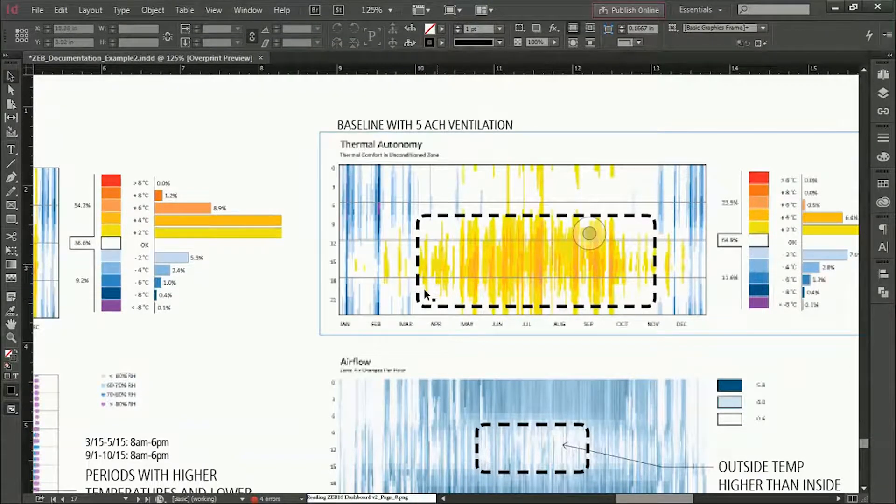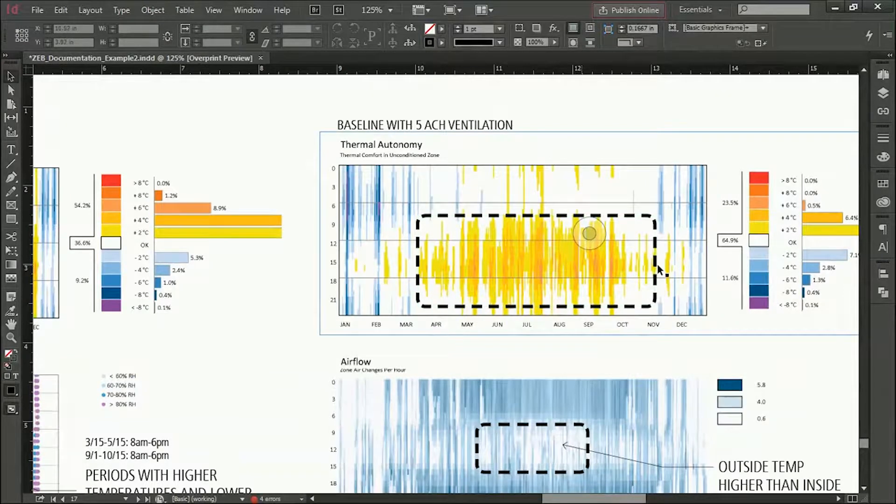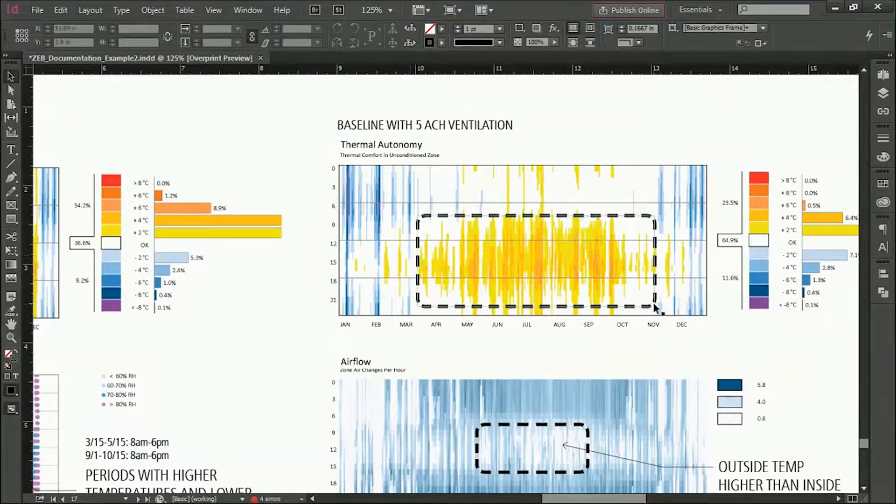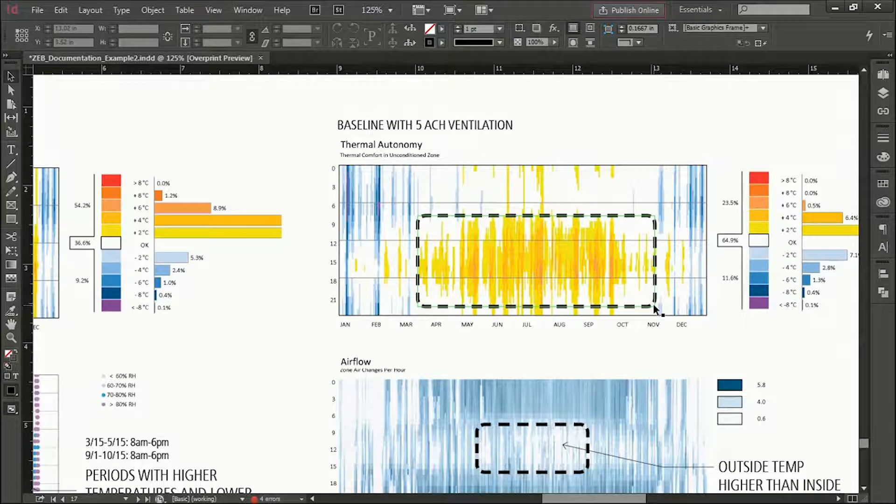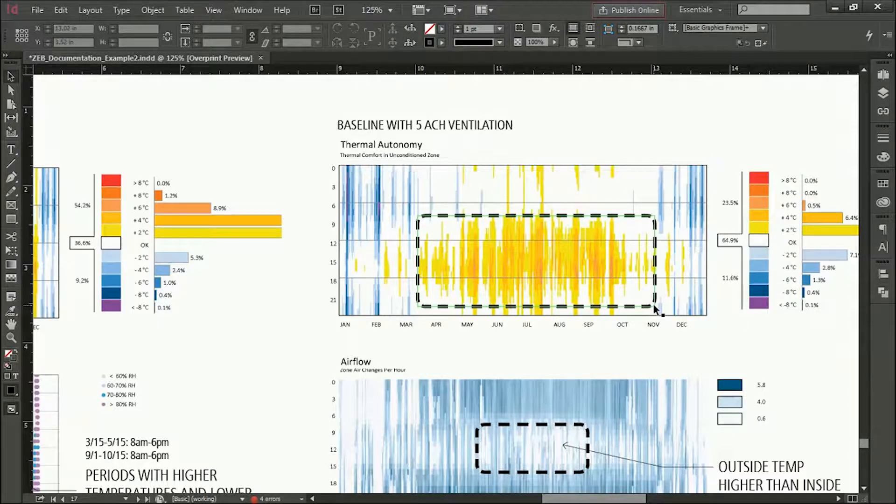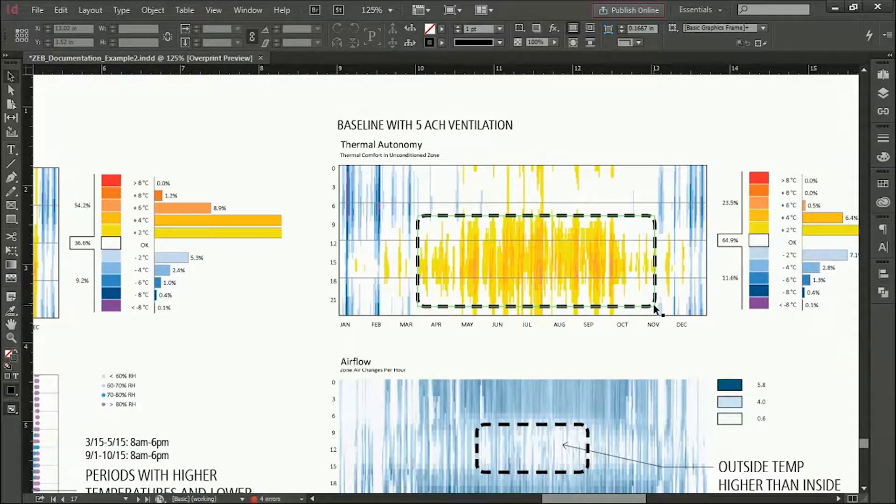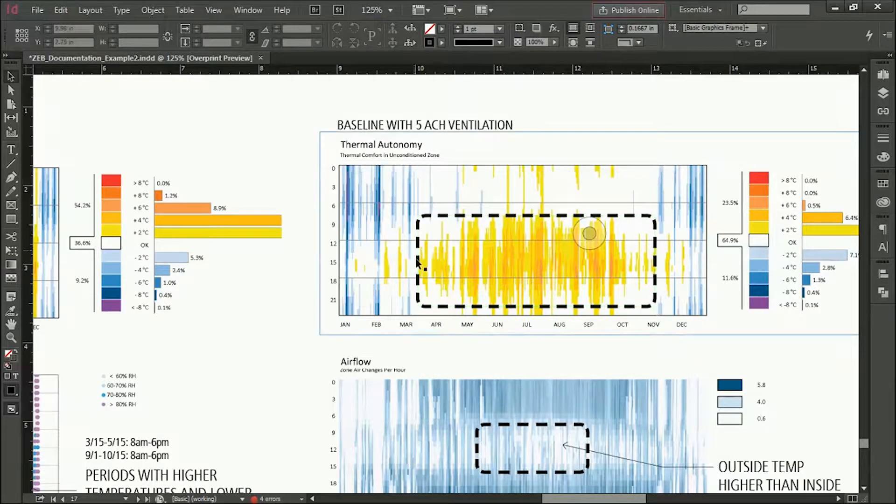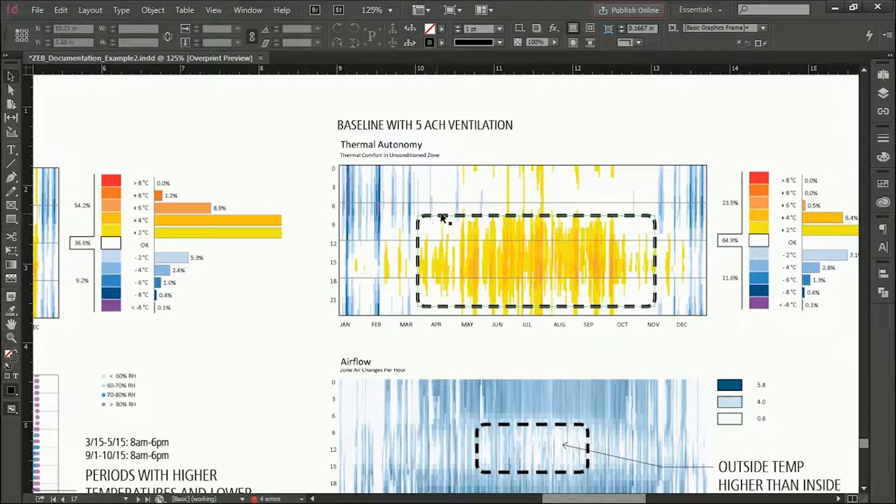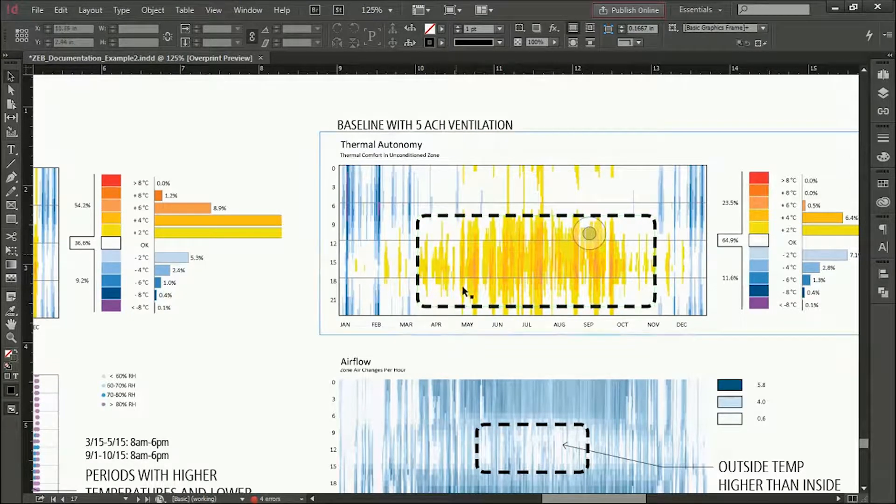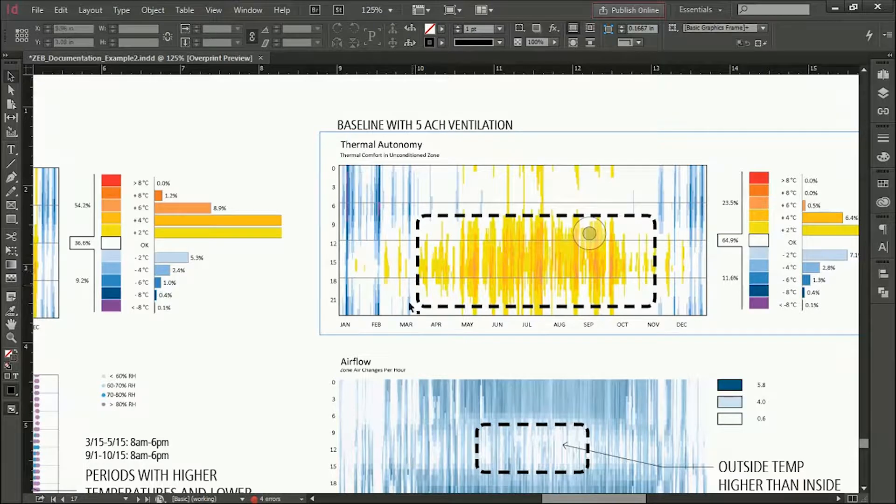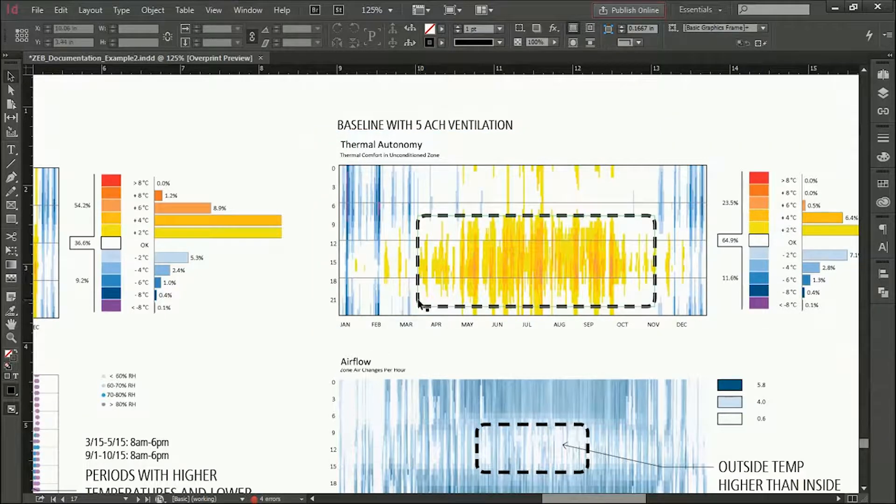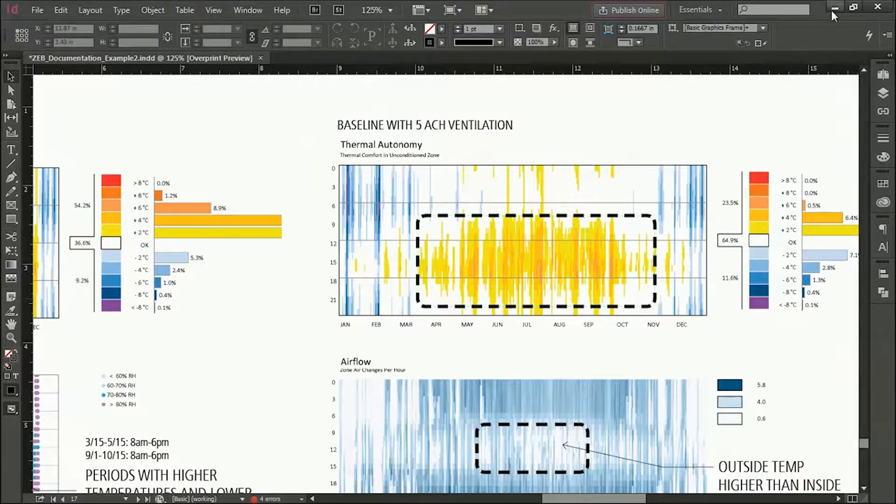We can see that the fans would be useful anytime that the interior is going to overheat. If you have enough air flow with natural ventilation, then you won't need the fans. But fans also don't use very much energy, so to simplify things, let's just assume the fans are going to run for this entire period from 8 a.m. to 6 p.m. from mid-March to November.